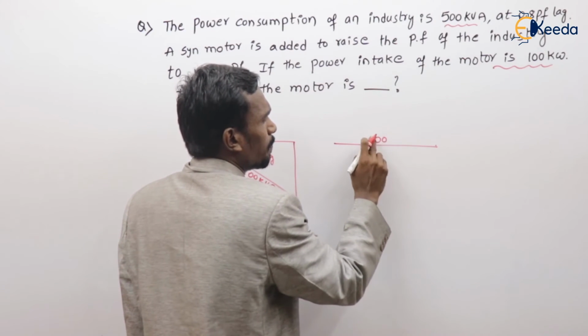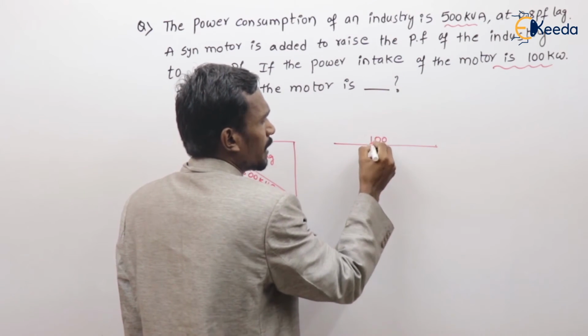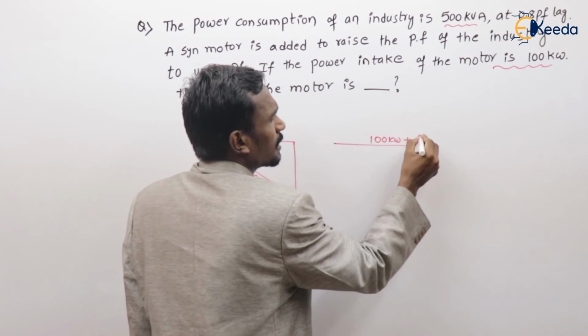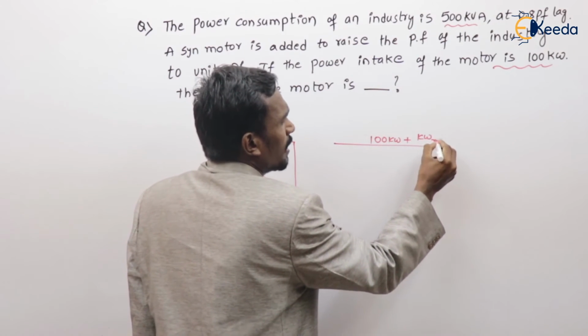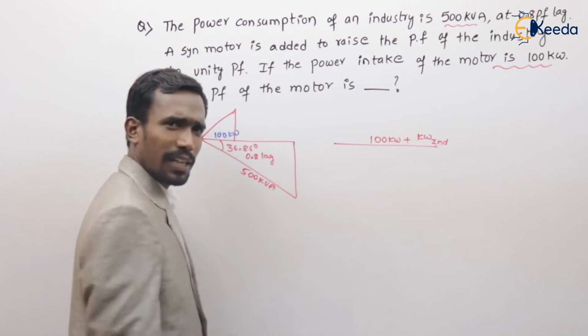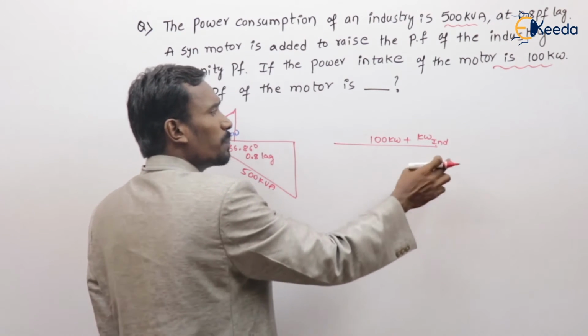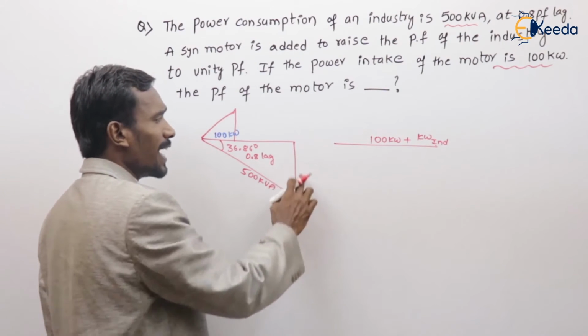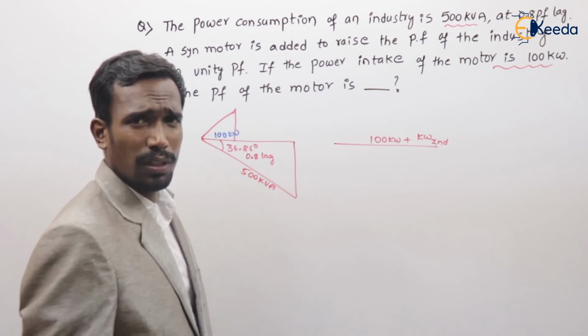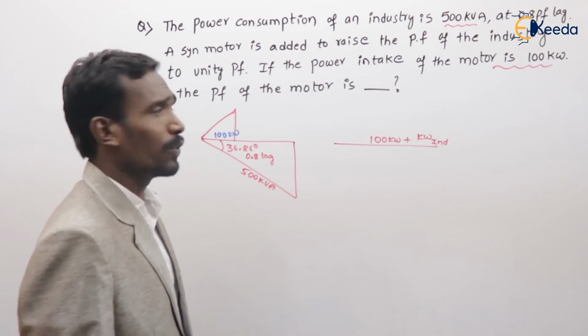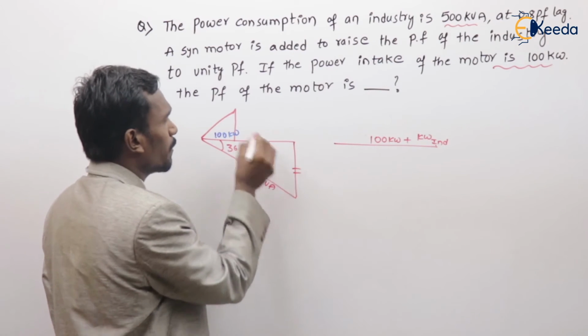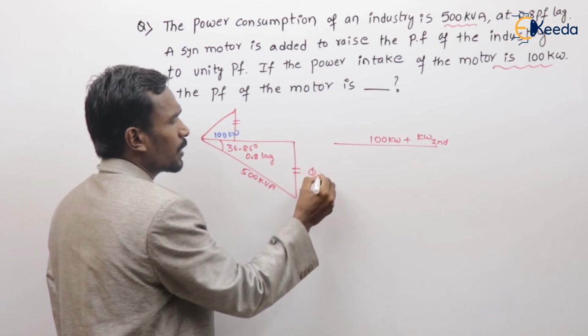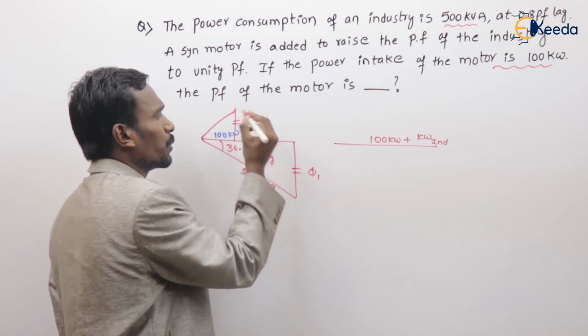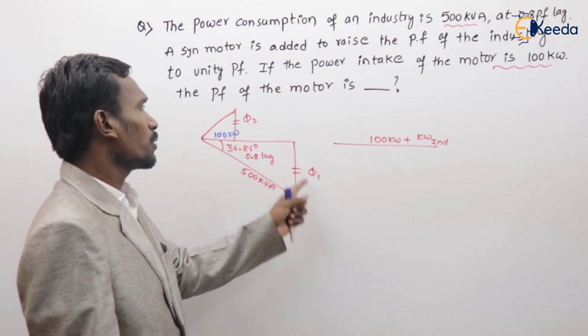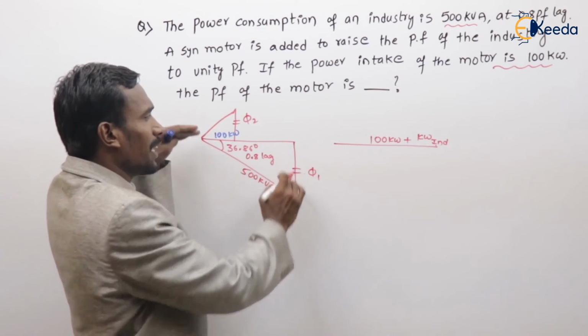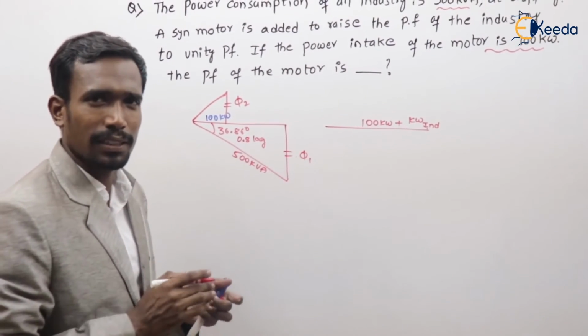This is the 100 kilowatts plus the kilowatts of the industry, the actual industry. But the reactive power should be zero. How can we get that zero reactive power? This reactive power should be equal to this reactive power. Q1 should be equal to Q2, then both get cancelled out and the power should be like this.